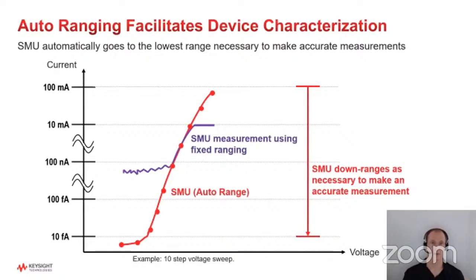When you're in a given measurement range, you get about 5 digits, or 5 decades, of accuracy below that range. So if you're in, for example, a 10 milliamp range, you can't go down and measure nanoamps or picoamps accurately, because you actually need to go to a lower measurement range. So you should never try to make low-level measurements in a fixed range, or even a limited range, if you set the range higher than the range you actually need.